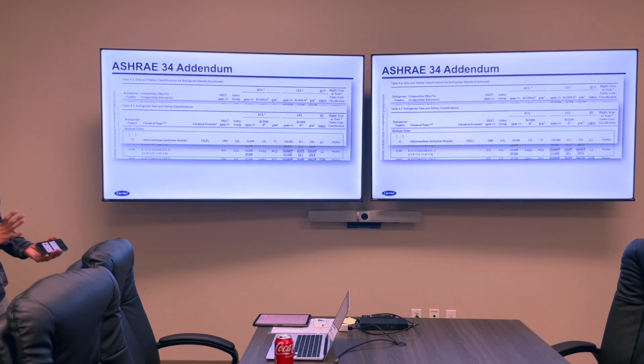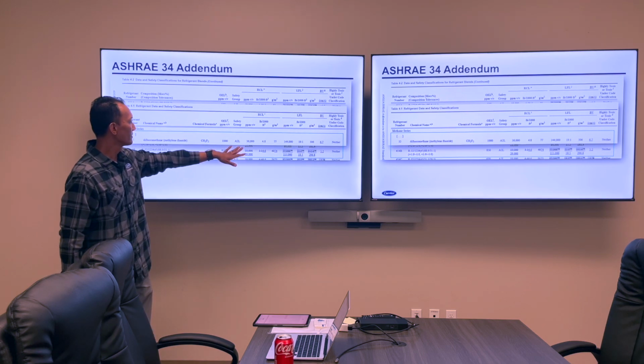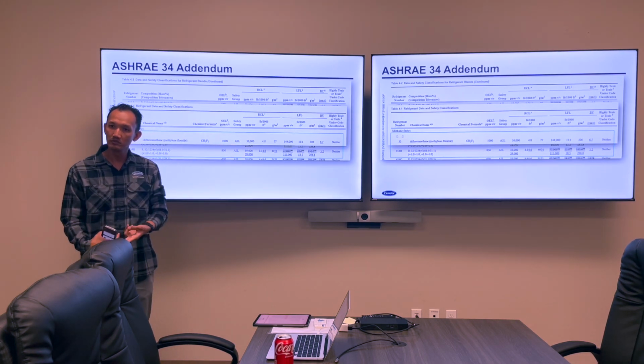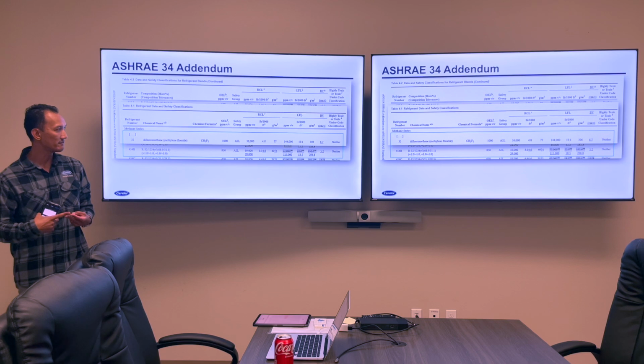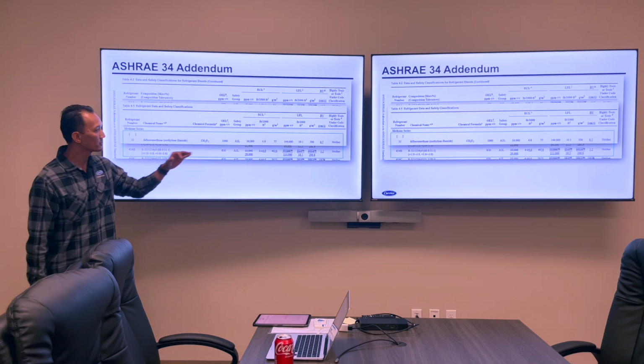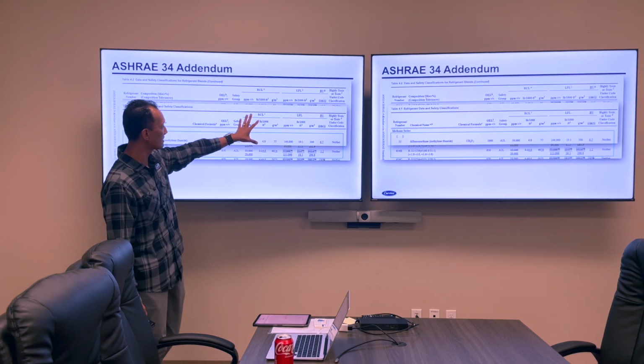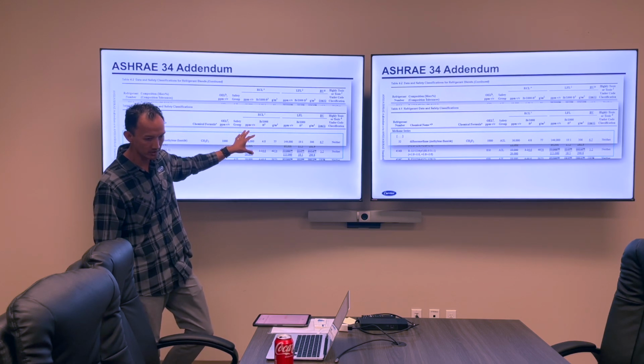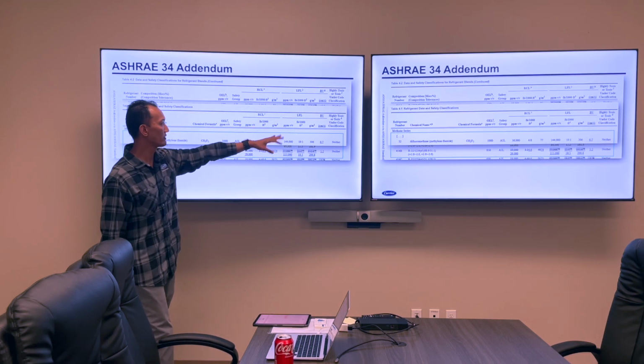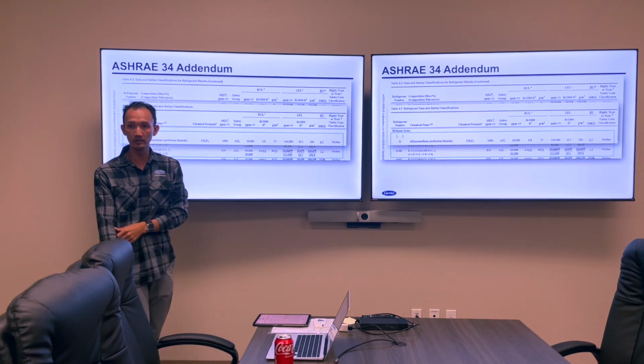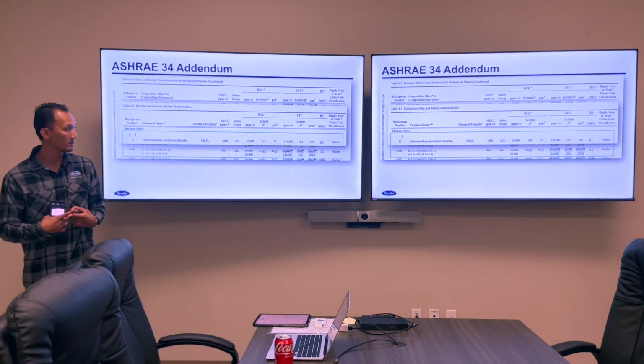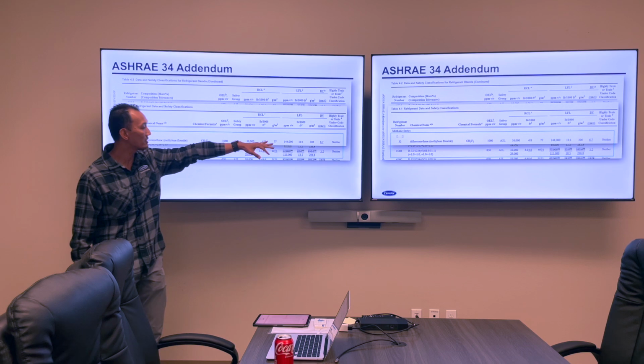All right. With these new A2L refrigerants, we have to be concerned with their slight flammability, right? A2L means they're not toxic, but slightly flammable. So with ASHRAE, we have to look at not just RCL now, which stands for refrigerant concentration limit. We have to worry about LFL, which is lower flammability limit, since these refrigerants are slightly flammable. So RCL is based off of LFL.